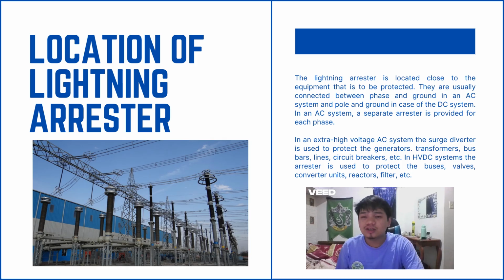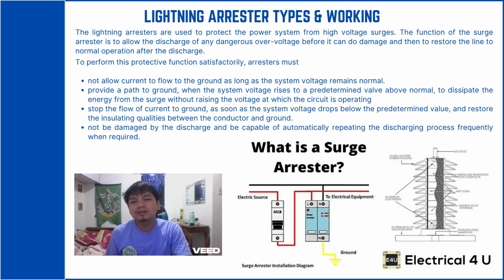So in extra high voltage AC systems, these surge diverters are used to protect major components such as generators, transformers, bus bars, transmission lines, and of course circuit breakers. Meanwhile, in an HVDC system, lightning arrestors are placed to protect buses, converter units, valves, reactors, and filters. So let us now talk about the lightning arrestor types and working.